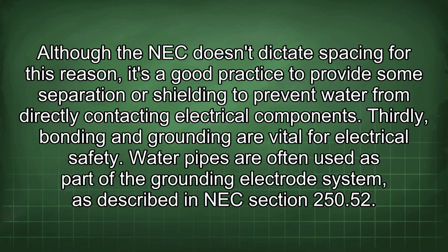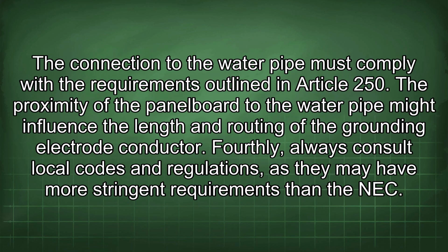Thirdly, bonding and grounding are vital for electrical safety. Water pipes are often used as part of the grounding electrode system, as described in NEC Section 250.52. The connection to the water pipe must comply with the requirements outlined in Article 250. The proximity of the panel board to the water pipe might influence the length and routing of the grounding electrode conductor. Fourthly, always consult local codes and regulations, as they may have more stringent requirements than the NEC.